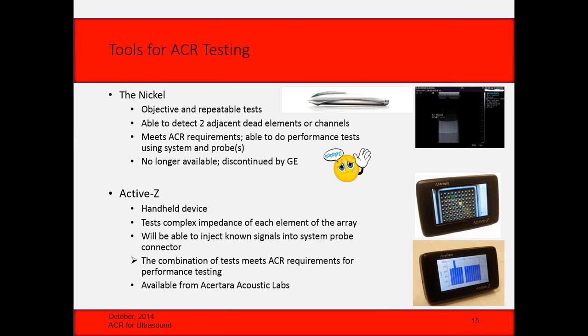The folks at Acertara Acoustic Labs that developed this are working on it and already have it working in a prototype. They have a way to inject a known signal level into the system, into the probe connector of the system. So that means that once that's developed, by having the combination of those things, the ability to test the complex impedance of the probe, and then the ability to inject a known signal into the system and measure the sensitivity of the system, that will then give us the ability to meet the ACR requirements. So that's Acertara Acoustic Labs that has the ActiveZ device.